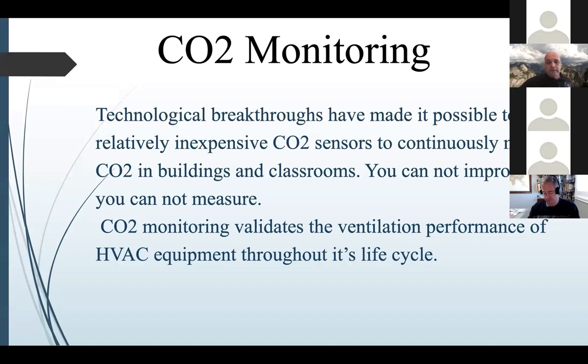CO2 monitoring is something I've adopted over the past 2 years. I now have well over 1,000 CO2 monitors throughout Eastside, in almost every classroom. They're inexpensive, easy to maintain, and provide a ton of information. Technology has gotten so cheap now that entry-level CO2 monitors run anywhere between 150 to 200 bucks. You can buy handhelds or desktops, and there are complete monitoring systems on the market today that can monitor large campuses and send you alerts. There's quite a bit out there on CO2 monitoring, but it's a really good way to validate whether your building is getting enough ventilation.